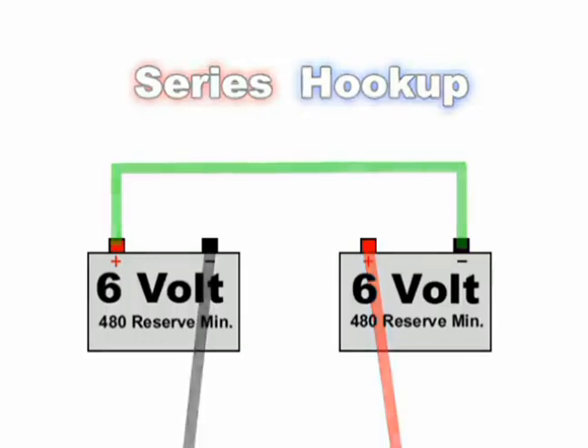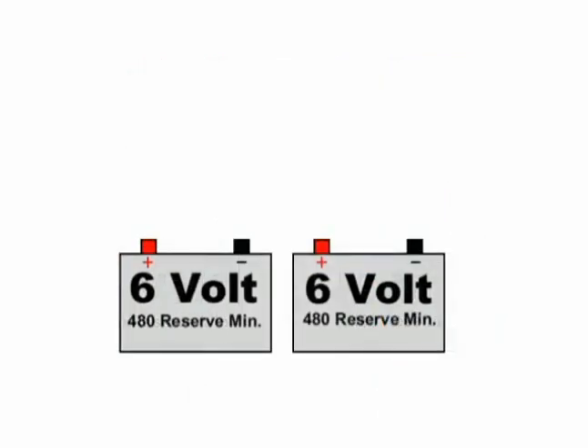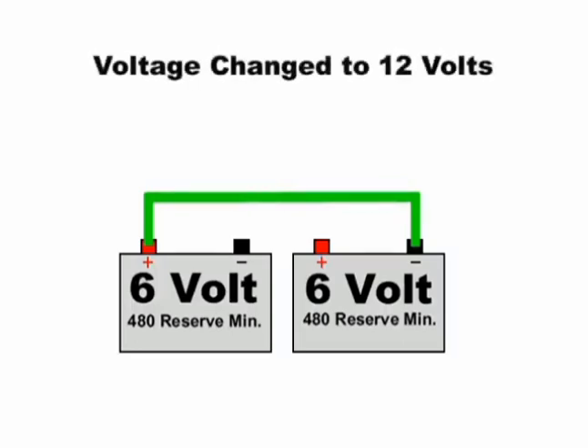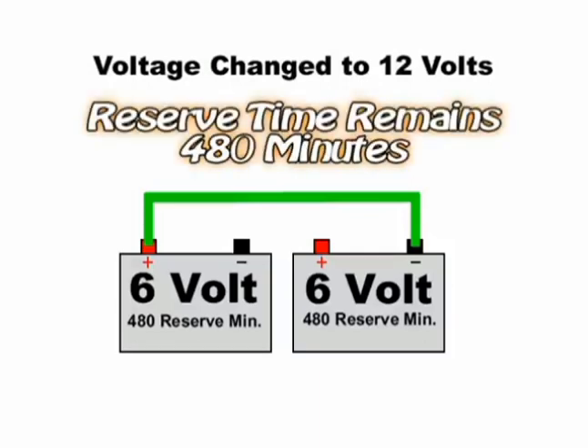Here's how we do that. With the batteries close to each other, a jumper wire is put between one of the positive posts of one battery and the negative post of the other. Notice that leaves a positive and a negative post free. We've just made a 12-volt battery system with two 6-volt batteries and a reserve capacity of 480 minutes. Unlike the parallel system, when you hook in series, you double the voltage, but the reserve stays the same.